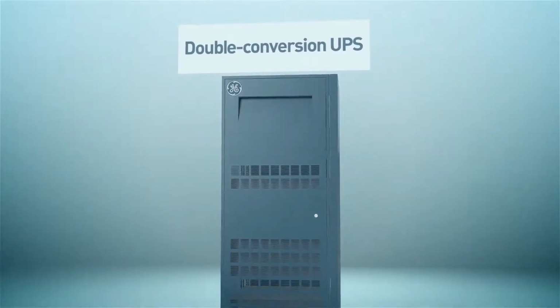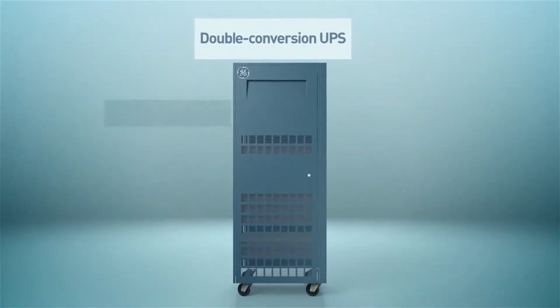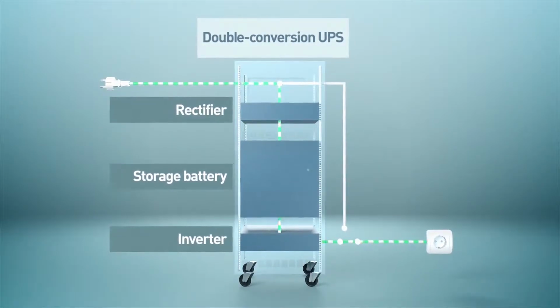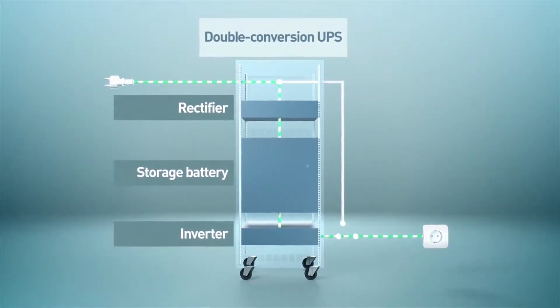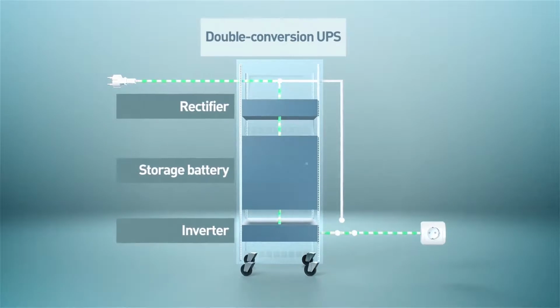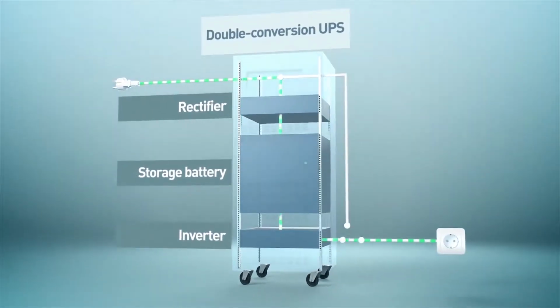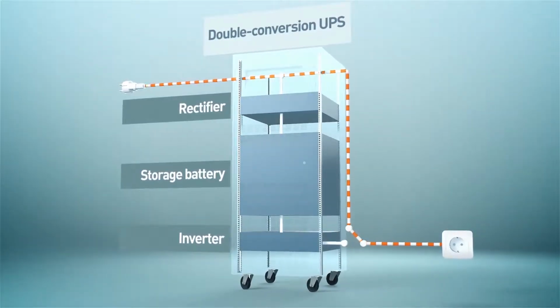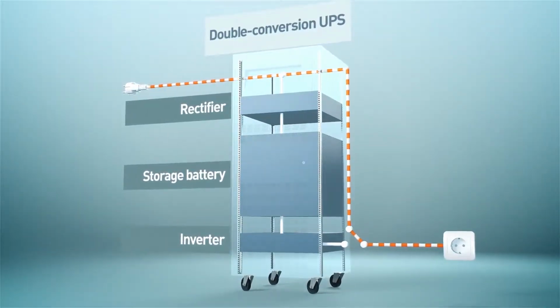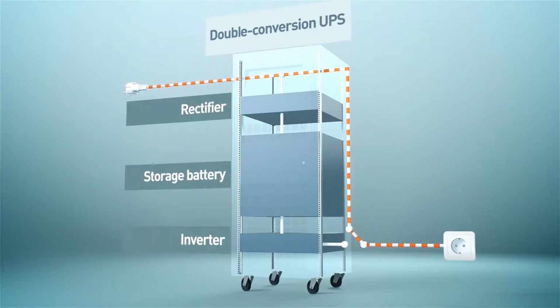We have launched the TLE UPS, which is the most efficient UPS in the world, with 97% efficiency, double conversion. The most reliable UPS devices are double conversion ones. Unlike the first two types, the inverter there operates constantly, giving stable AC power without noises and splashes. In such devices, there is additional insurance, automatic bypass. This is a separate bypass line, which can feed objects directly from the mains if the inverter suddenly fails.